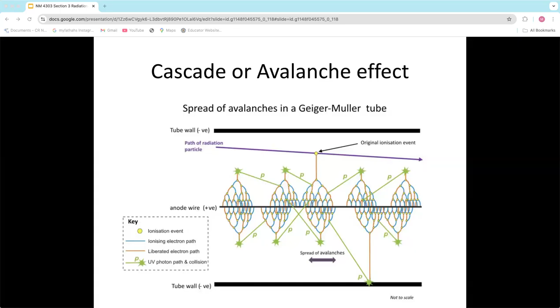So here I want to separate the difference between an ionization type meter and a Geiger-Muller meter. Really the only difference is that it's a gas filled detector, but the amount of voltage we're applying changes how it functions and reacts. These are the two things I want you to keep in mind, and their differences when it comes to boards and testing.